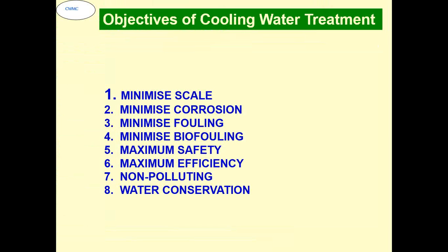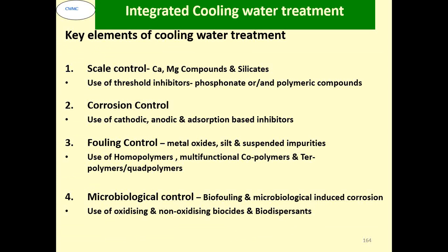Cooling water treatment. Objectives are to minimize scale, minimize corrosion, minimize fouling, minimize biofouling, maximum safety, maximum efficiency. It should be non-polluting. Water conservation has to be there. Scale control: calcium and magnesium compounds and silicates. Generally use threshold inhibitors like phosphonate and or polymeric compound combinations.